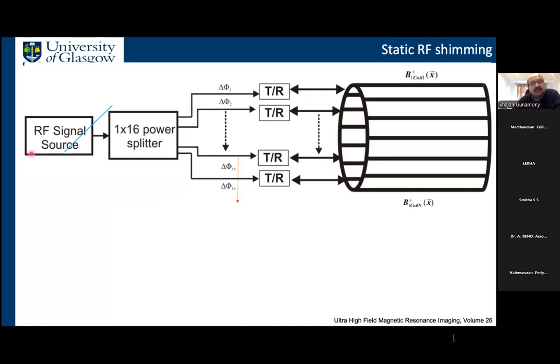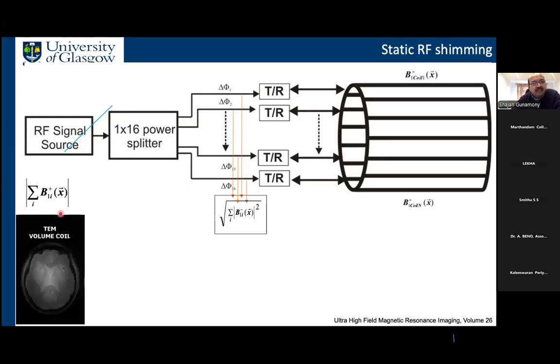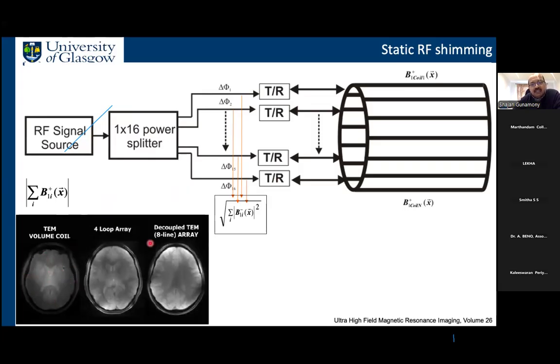So the way this was done was, this process is called static RF shimming. We have a single RF amplifier. The output from the amplifier is then fed to a power splitter, which gives outputs of equal amplitude. We can then change the phase of the current that is flowing through each of these outputs, and that way we can manipulate the field. Okay, that's what happens during transmit. When we receive, we acquire the signal just like in a conventional receive array. And here, this is the image produced by the volume coil. So you have the center brightening and the darker periphery. And with this kind of a setup, we recover the signal in the periphery, and we get a much flatter looking image.